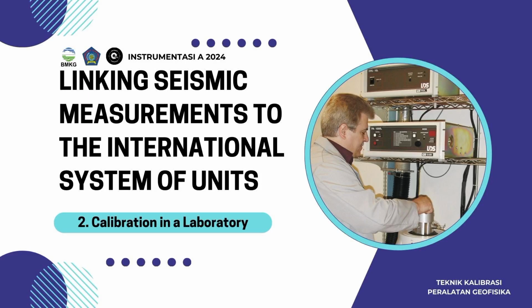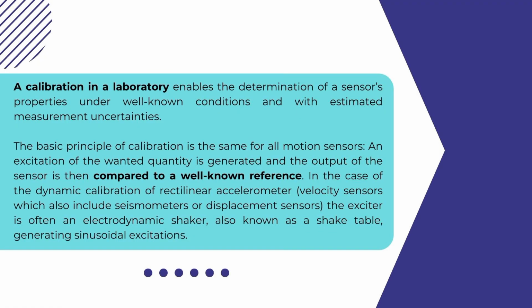Today, we, Group 2, are going to talk about linking seismic measurements to the International System of Units. But before doing so, firstly, we're going to talk about calibration in a laboratory. A calibration in a laboratory enables the determination of a sensor's properties under well-known conditions and with estimated measurement uncertainties.